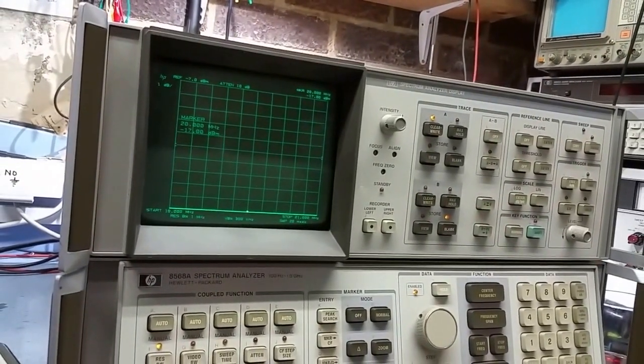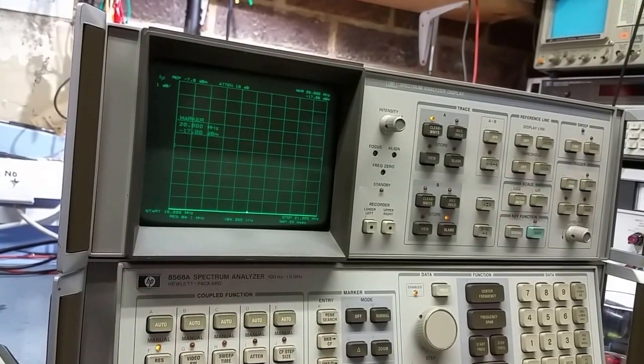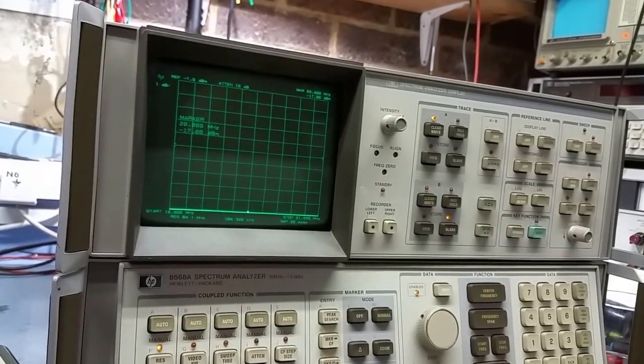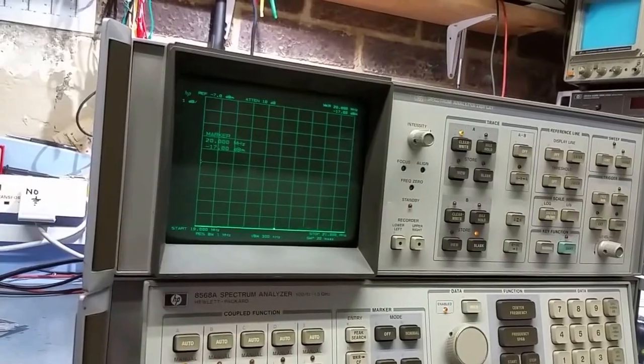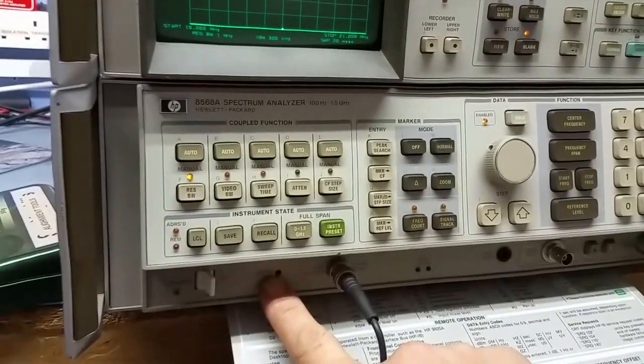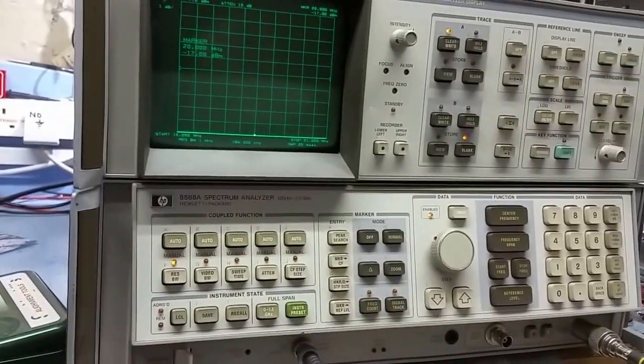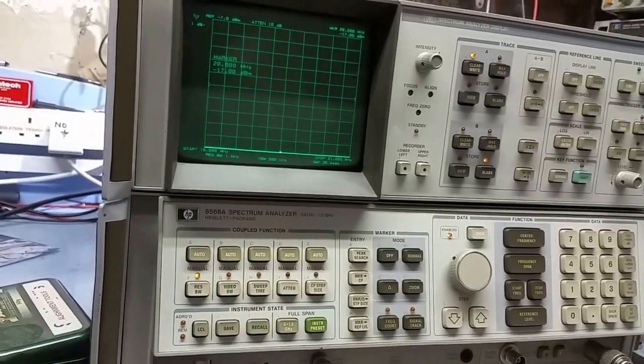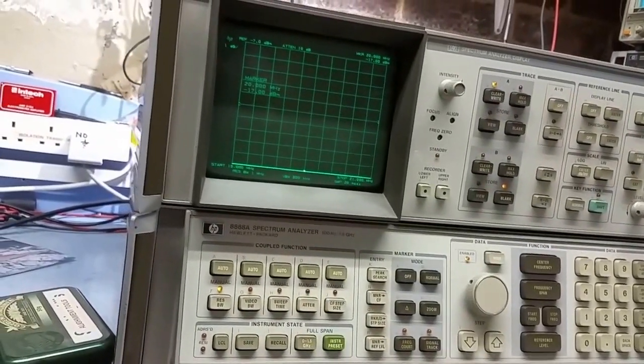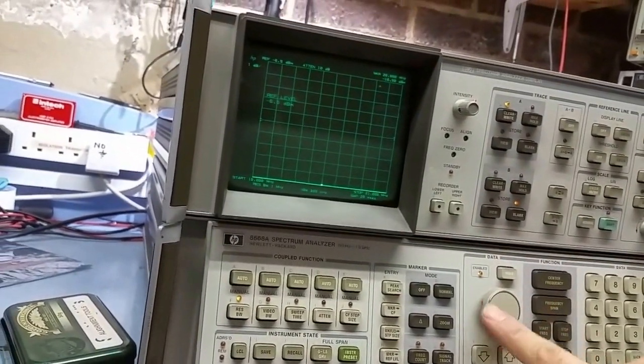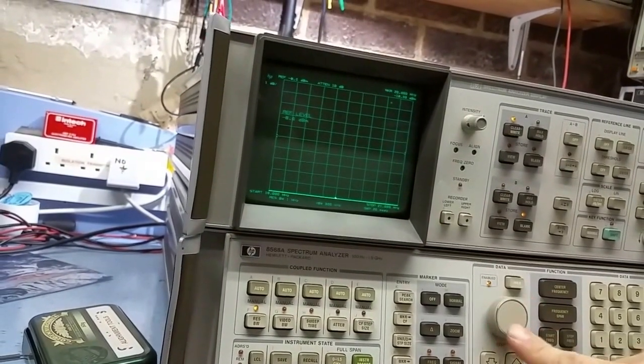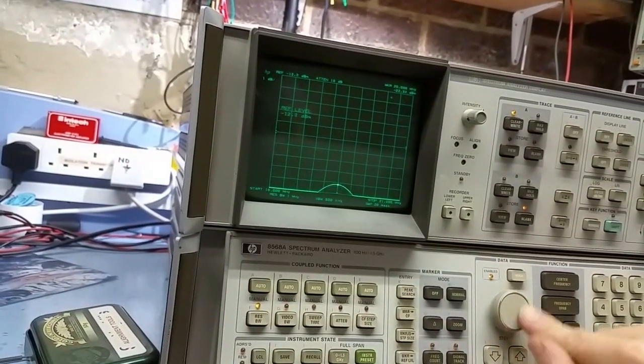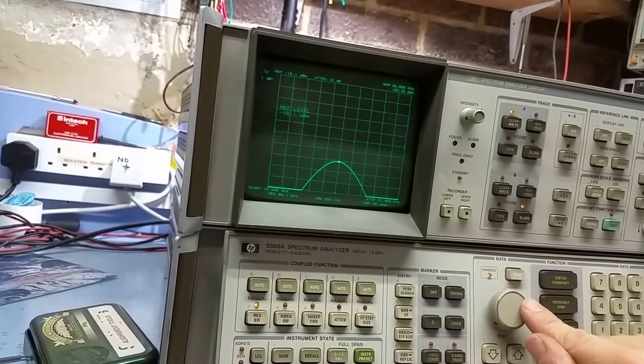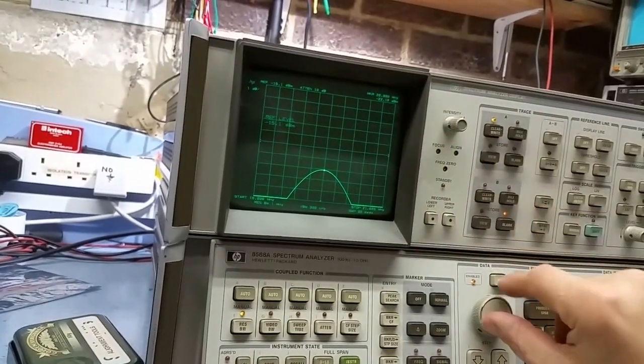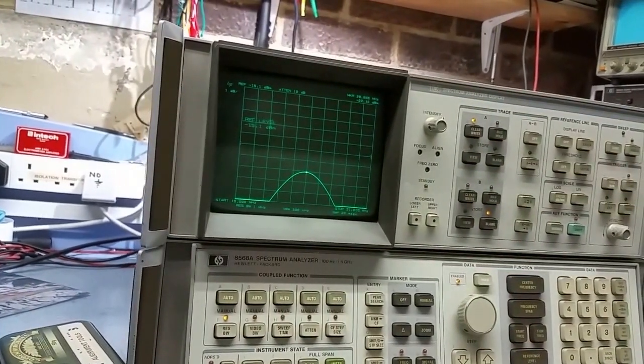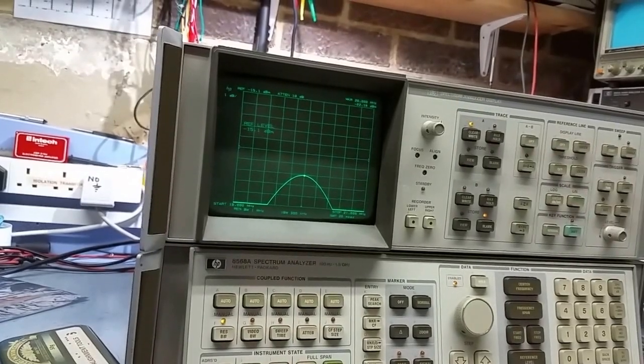So we recalled channel 8, and what it says is adjust the amp calibration, which is this box down here, for a marker of -10 dBm. Now I can't get anywhere near that. If I bring the reference level up, I'll show you what's happening.